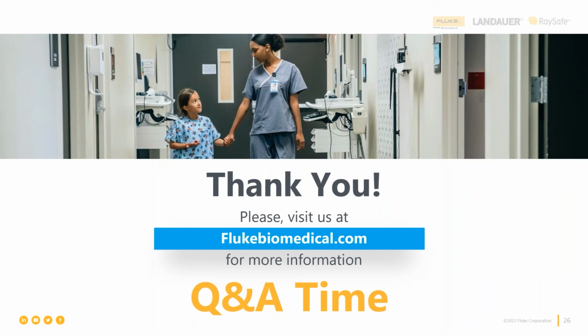Okay, perfect. We have just a couple more minutes, so we'll just do a couple more questions here. If the medical device doesn't have a metal post, how can I test it for electrical safety? Okay, so we're talking about the protective earth test pin, to protect the accessible ground on a class 1 medical device. And as I said, not all class 1 medical devices actually have this pin, so it's a great question. If there's no accessible ground, we're not allowed to go use some other ground for testing the medical device for ground wire resistance or leakage to ground of any kind. Therefore, you cannot do the ground wire resistance, you cannot do leakage to ground, and you cannot do the applied parts to ground, which would be the patient continuously conductive patient connections. You can't, because you're not provided with the right test point to be able to use. But you must always do the touch current test.